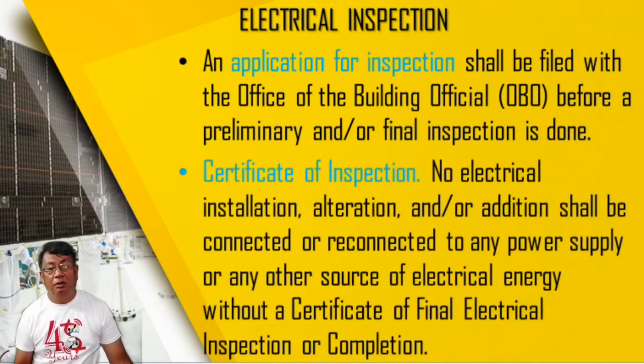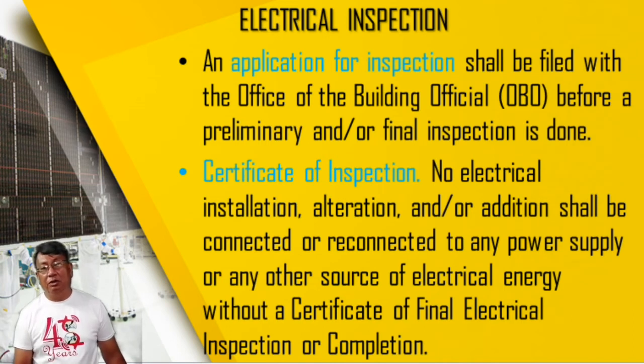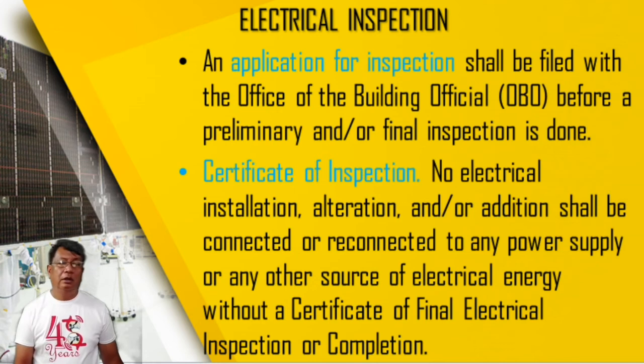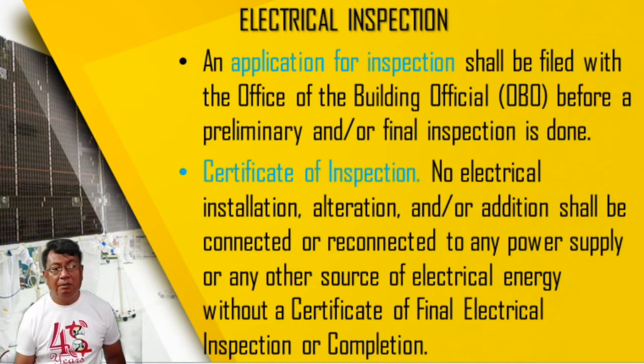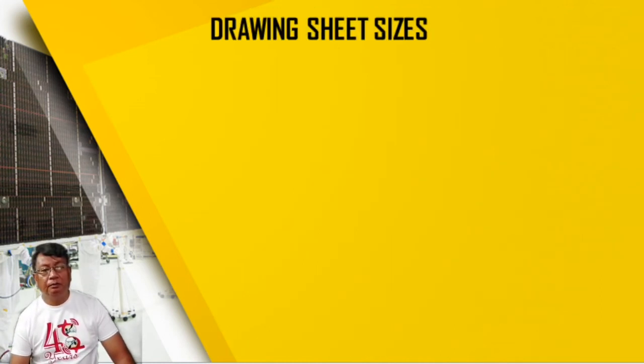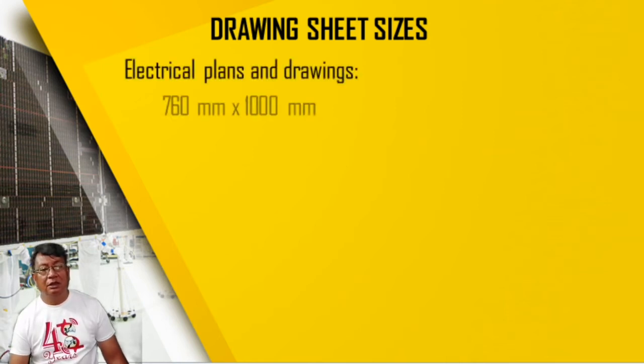Okay, so we have the certificate of inspection. No electrical installation, alteration and or addition shall be connected or reconnected to any power supply or any other source of electrical energy without a certificate of final electrical inspection or completion. So even the distribution utility has no authority to energize. They will be the one to supply electrical energy, but they are not authorized to energize the electrical installation without an approved certificate of inspection.